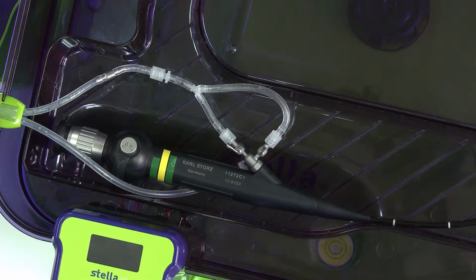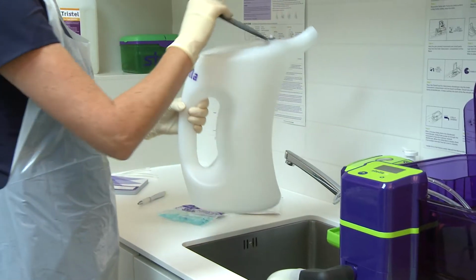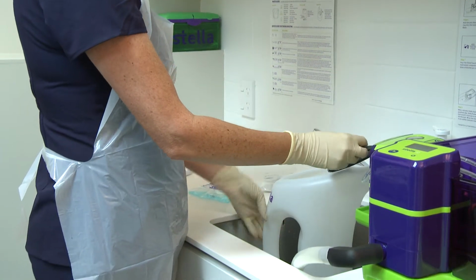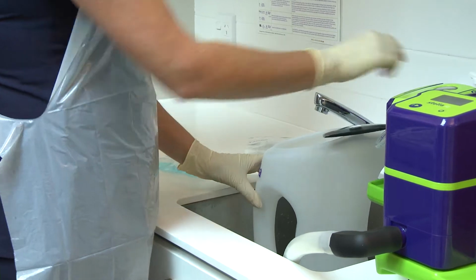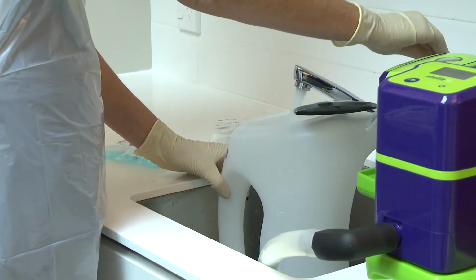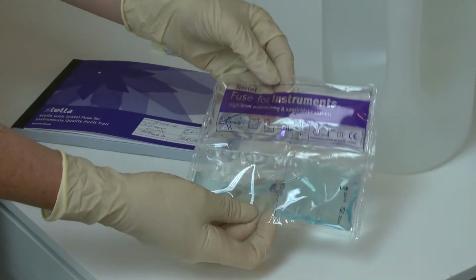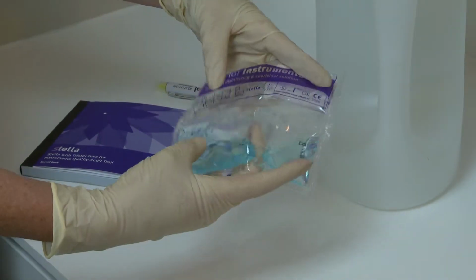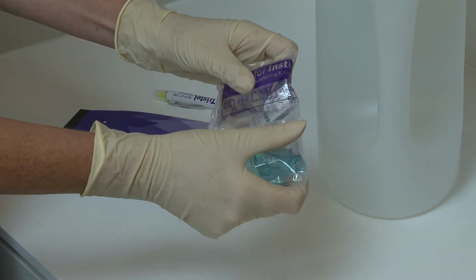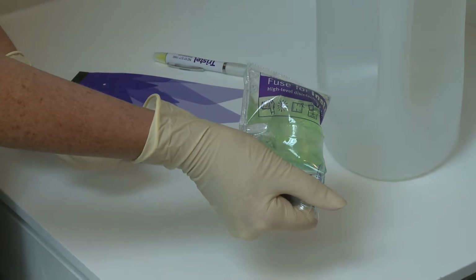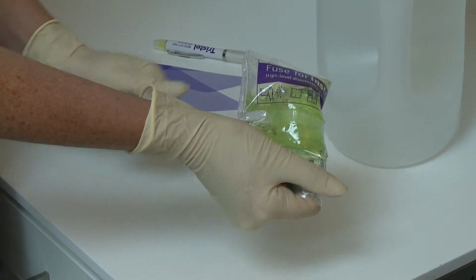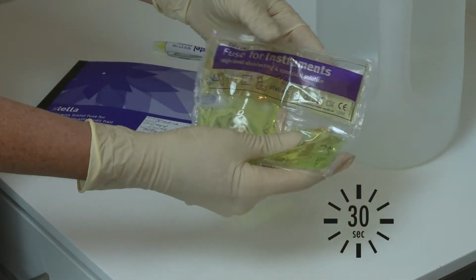Ensure the disinfectant pickup filter is in the base of the inner compartment. Make up 5 litres of Tristel Fuse for Instruments. Add 5 litres of ambient cold water to the Stella jug. Take 1 sachet of Tristel Fuse for Instruments. Fold the sachet in half and burst the contents through the centre seal. Move contents from side to side for 30 seconds.